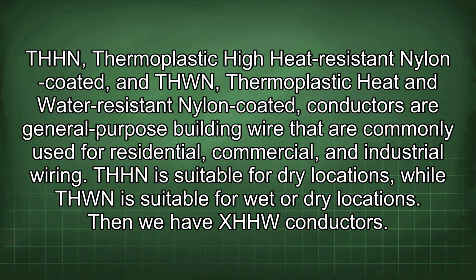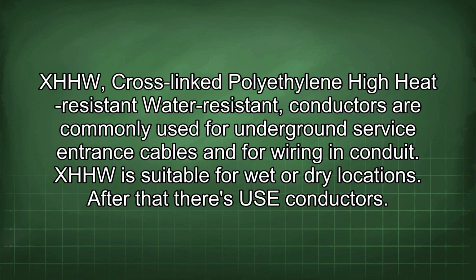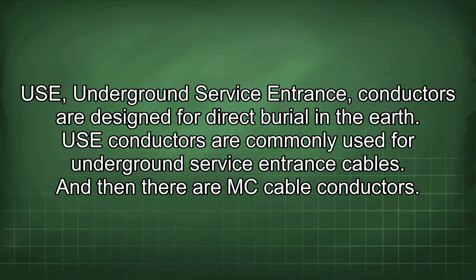Then we have XHHW conductors. XHHW, cross-linked polyethylene high-heat resistant water-resistant conductors, are commonly used for underground service entrance cables and for wiring in conduit. XHHW is suitable for wet or dry locations. After that there's USE conductors. USE, underground service entrance conductors, are designed for direct burial in the earth. USE conductors are commonly used for underground service entrance cables.